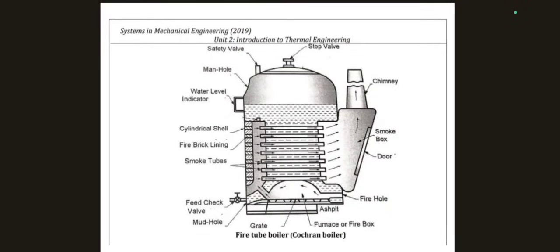In a fire tube boiler, the flue gases pass through tubes which are surrounded by water in the boiler shell. Example: Cochran boiler. Oil from the oil tank and air supplied by a blower produce hot flue gases, which pass from the fire tube to smoke tubes. The smoke tubes are surrounded by water, heating it. Steam rises from the upper water surface; gases enter the smoke box and are exhausted through the chimney. The boiler shell is surrounded by refractory material to reduce heat losses.